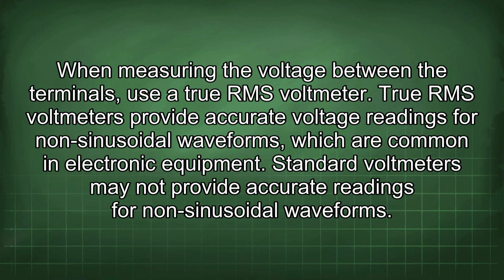When measuring the voltage between the terminals, use a true RMS voltmeter. True RMS voltmeters provide accurate voltage readings for non-sinusoidal waveforms, which are common in electronic equipment. Standard voltmeters may not provide accurate readings for non-sinusoidal waveforms.